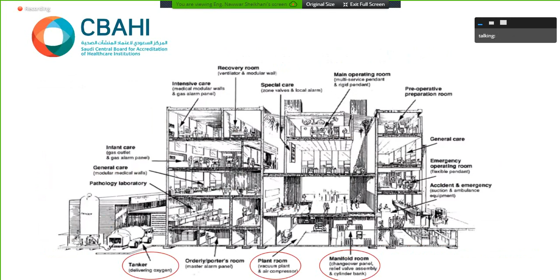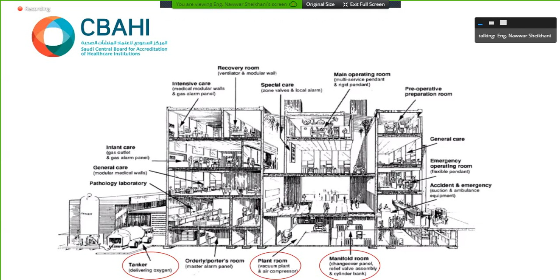This schematic shows the tanker delivering the oxygen to the tank, the LOX tank, liquid oxygen tank, the plant room where we have the vacuum plant and air compressor, and the manifold where we have the relief valve assembly, and we have the cylinder bank as well.